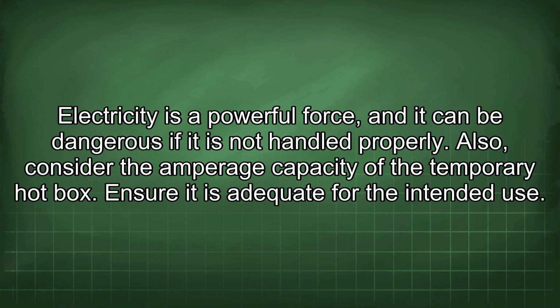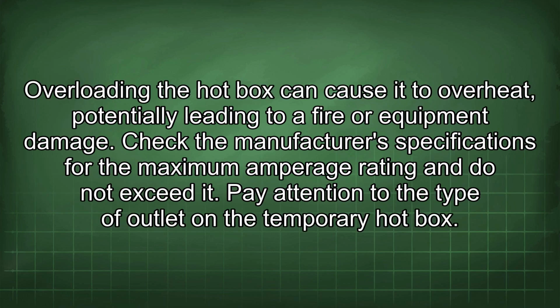Electricity is a powerful force, and it can be dangerous if it is not handled properly. Also, consider the amperage capacity of the temporary hot box. Ensure it is adequate for the intended use. Overloading the hot box can cause it to overheat, potentially leading to a fire or equipment damage. Check the manufacturer's specifications for the maximum amperage rating and do not exceed it.